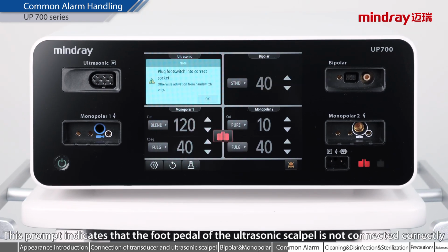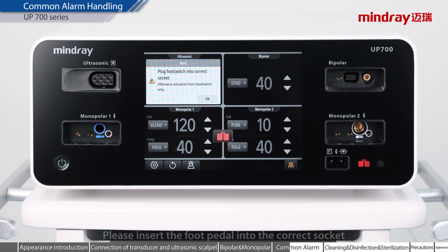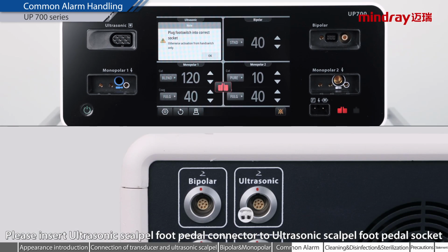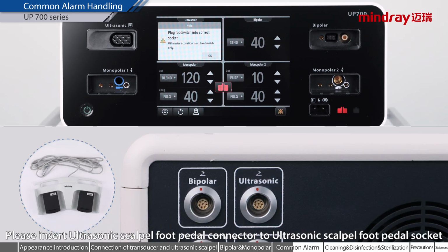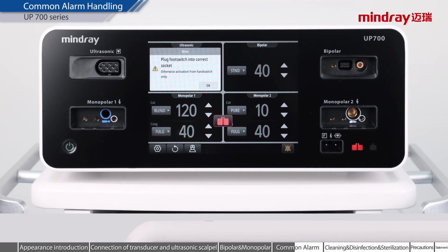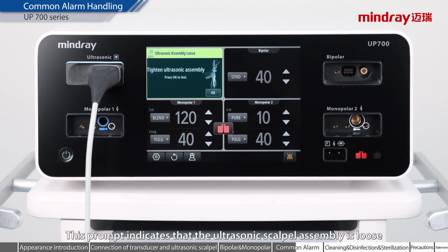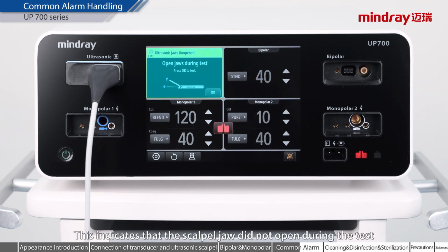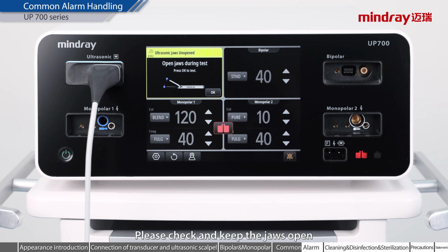This prompt indicates that the foot pedal of the ultrasonic scalpel is not connected correctly. Please insert the foot pedal into the correct socket. Please insert the ultrasonic scalpel foot pedal connector into the ultrasonic scalpel foot pedal socket. This prompt indicates that the ultrasonic scalpel assembly is loose. Please check and tighten the ultrasonic scalpel assembly. This indicates that the scalpel jaw did not open during the test. Please check and keep the jaws open.